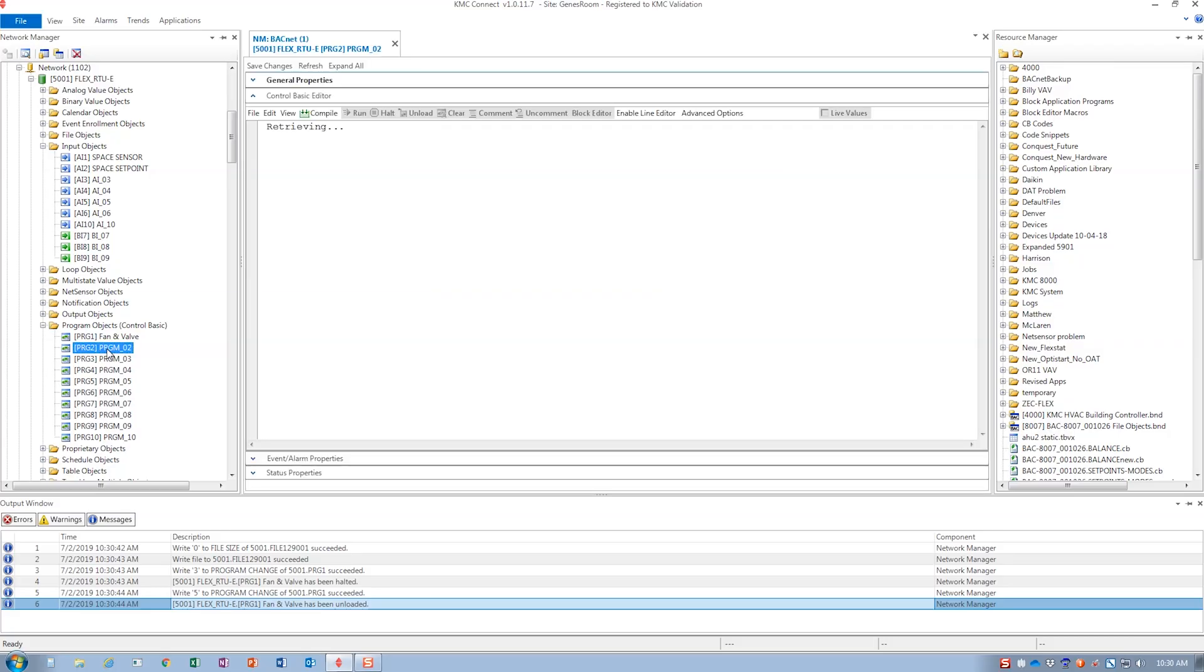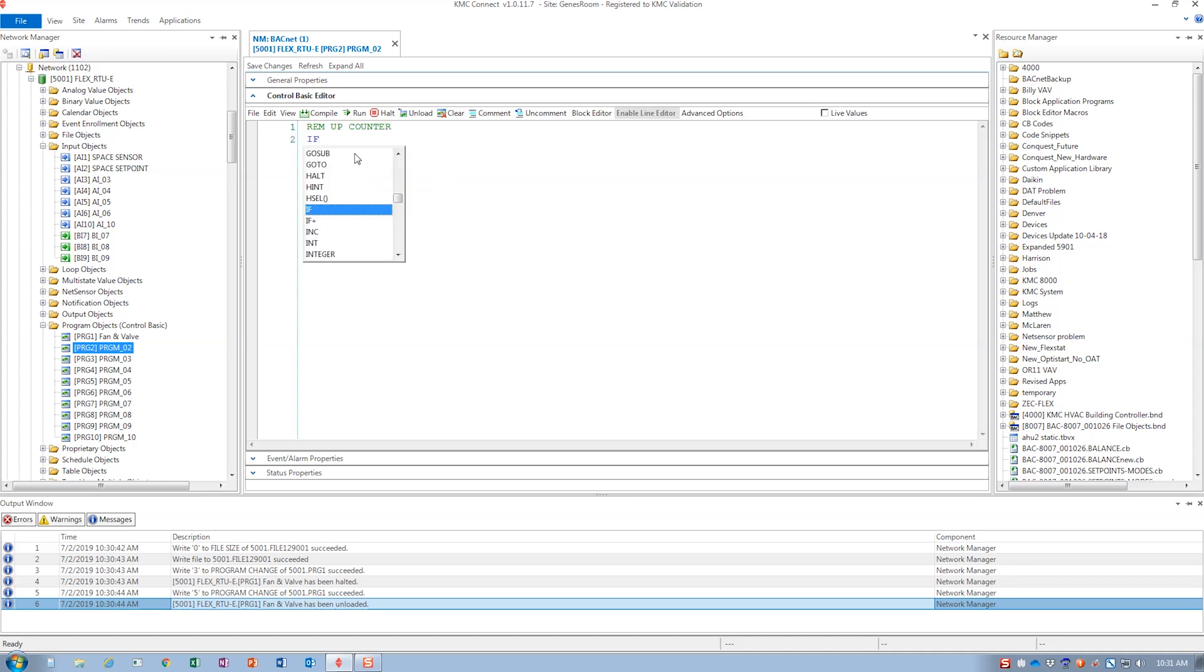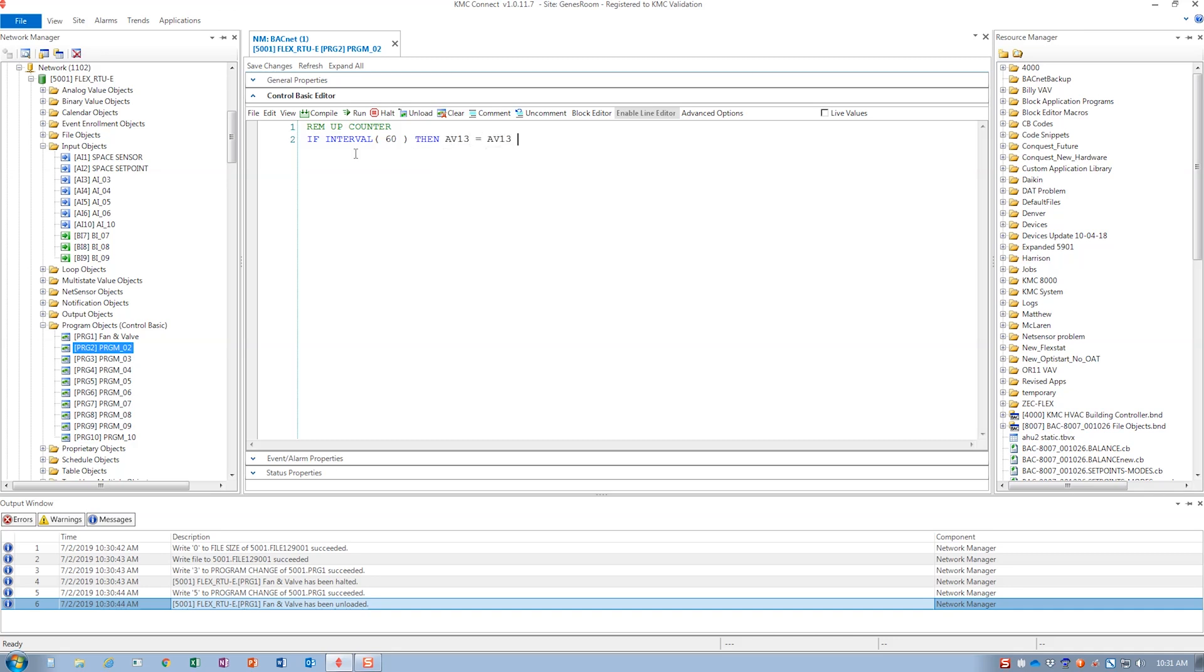Open a new Control Basic program. We are going to start with a REM statement so we know what the program's function is. For this comment, we are going to put up counter. Now, let's start with an interval example. If interval 60, then AV13 equals AV13 plus 1.